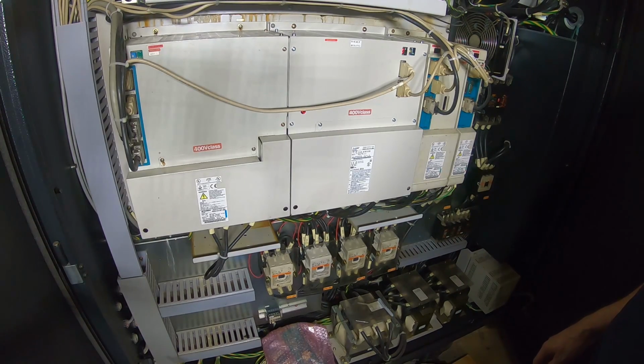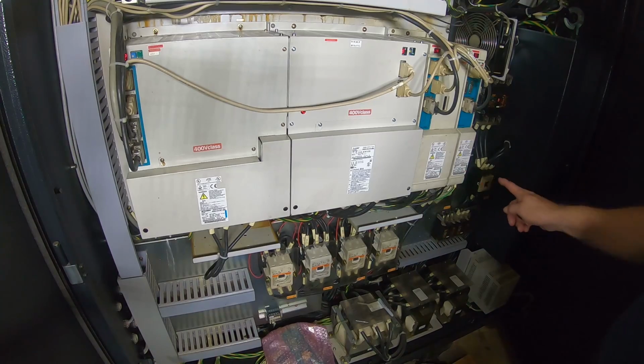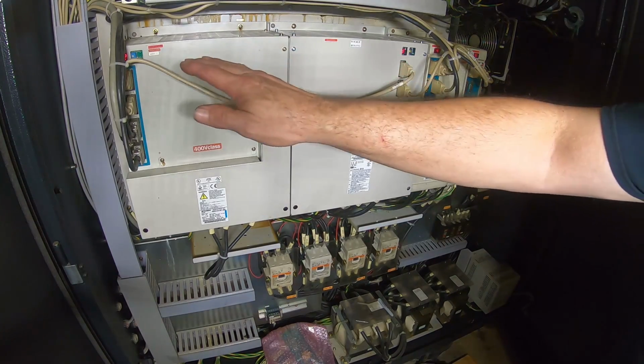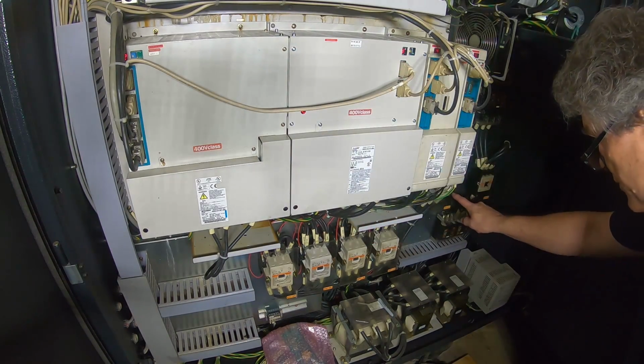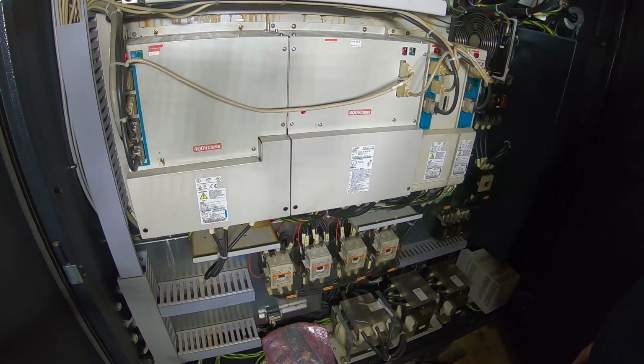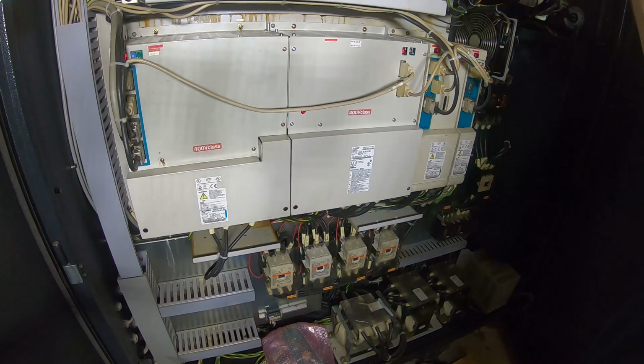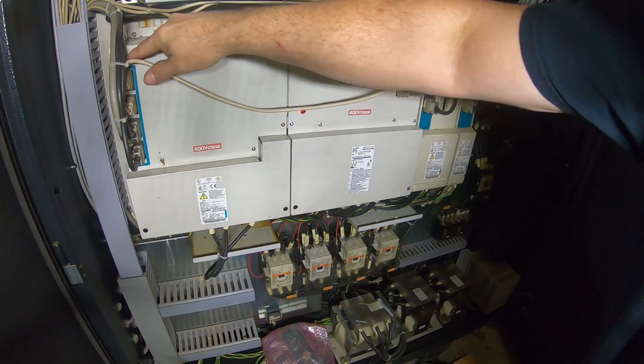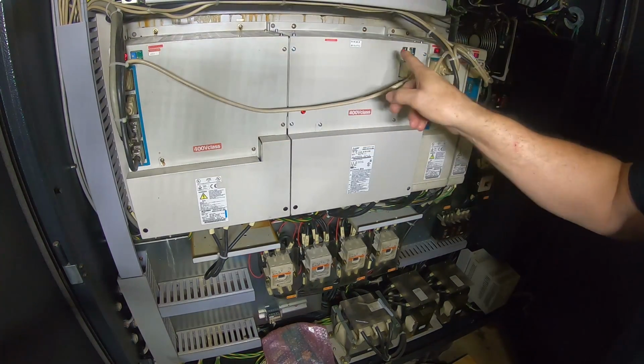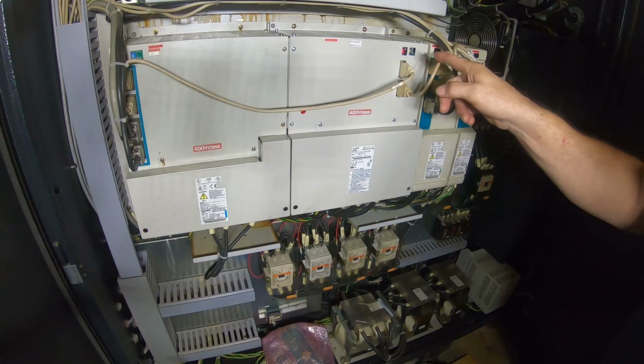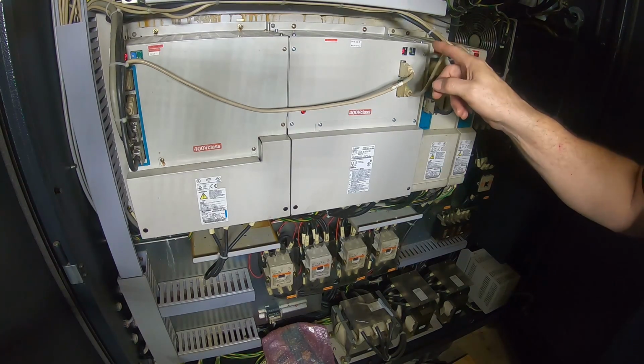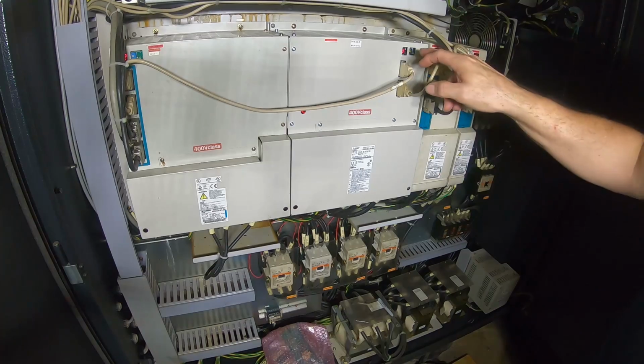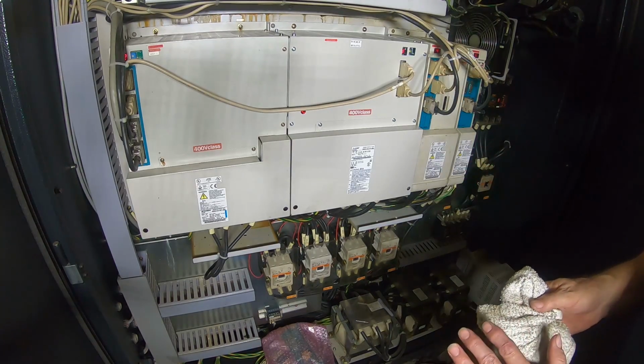There we go. Now pull that relay in. Awesome, it's perfect. See, it pulls this relay in when the servo power comes on, and all of these are doing good now. Before we had alarm 79, an error code, and an A or something on this LED, and it's all showing good now.